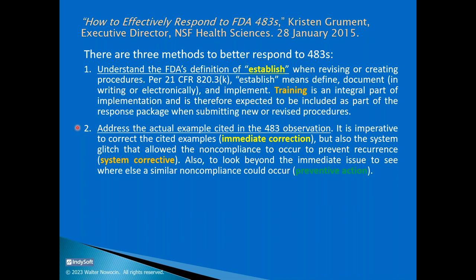companies tend to shoot themselves in the foot because they don't do what they say they did or have objective evidence. Same way when they respond to FDA warning letters, they don't address the immediate correction, but they also need to identify the system glitch that allowed the noncompliance to occur to prevent reoccurrence, which is what they call a system corrective. And then look beyond, which I told you before, to see where else a noncompliance could occur, which is what they classify as a preventive action. So in a 483, Kristen recommends, and you can see from the FDA this is an expectation, that organizations do an immediate correction, a system corrective, and then a preventive action.